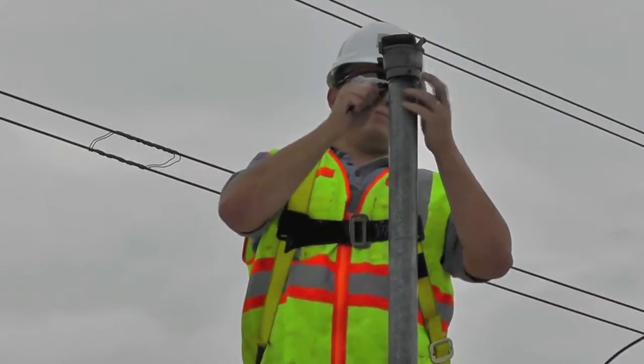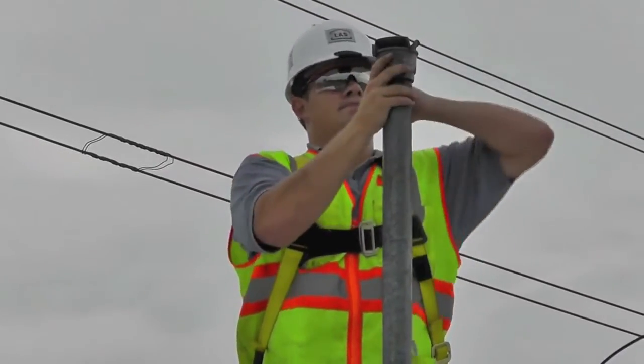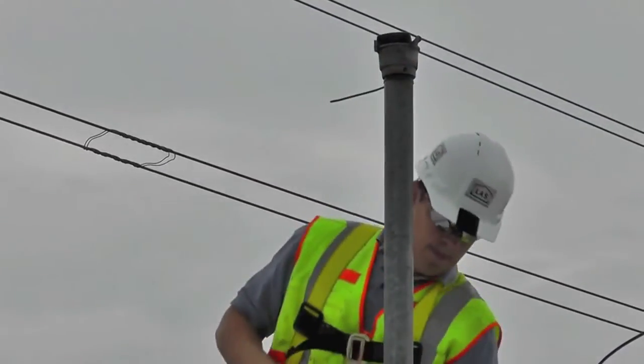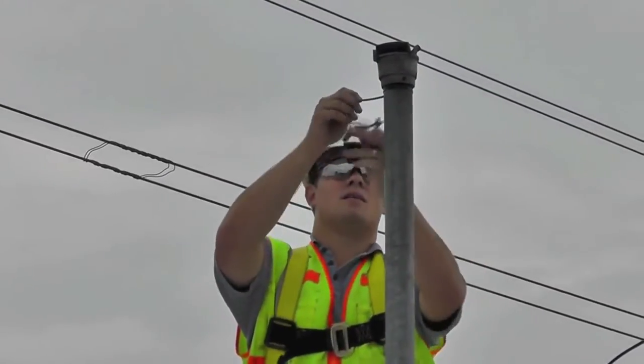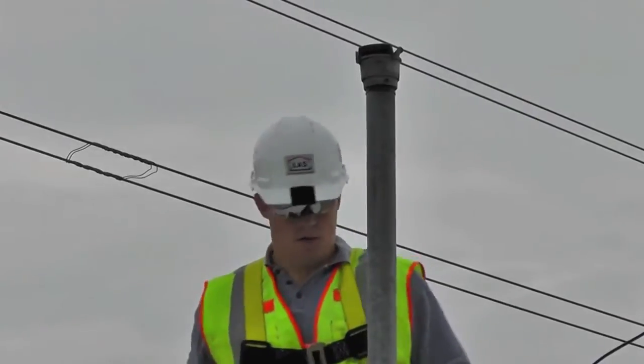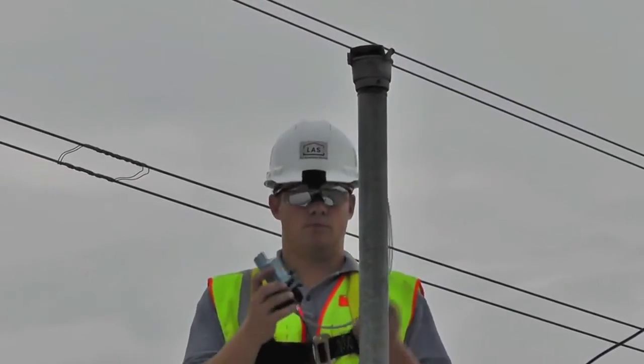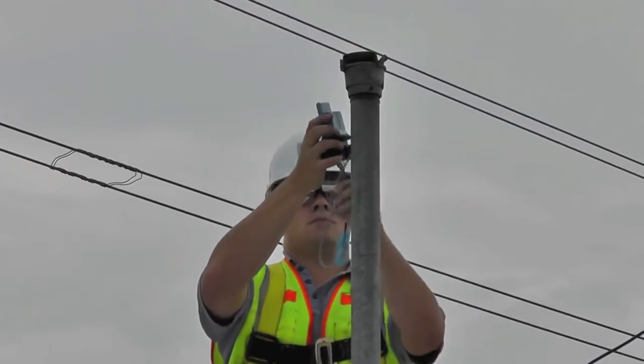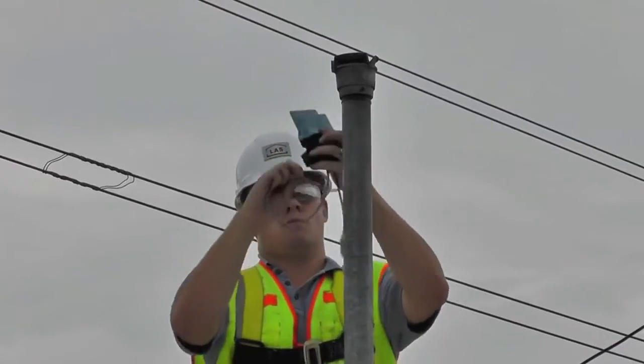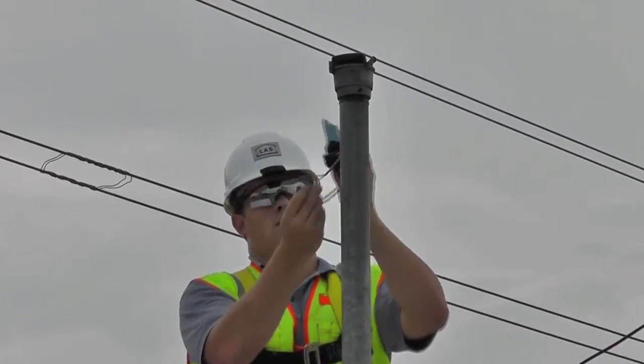The excess cable is fastened to the breather tube with zip ties. We then create what is called a service loop in the cable so that no water can run up the cable and possibly into the unit. The loops are secured and the monitor is strapped to the breather metallic band straps so that a neat and tidy installation is complete.